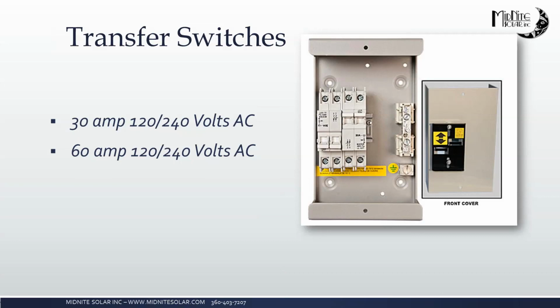So essentially what a transfer switch does is it takes a common either load or source, and it will feed it from 2 isolated sources or loads, if you will. So if you've got 2 generators, they both come into this switch. The 2 generators never will physically see each other electrically, and only one can ever be connected to the load at a single time. Just basically a simple isolation switch. It's available in a 30 amp and a 60 amp model. Both will be 120/240 volts AC. If it's 120 only you need, you can still use it, just don't use one pole of the breaker.